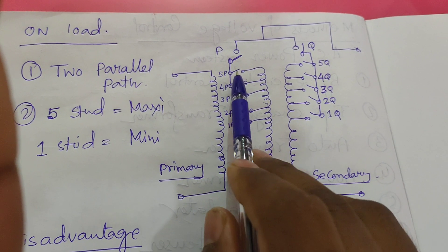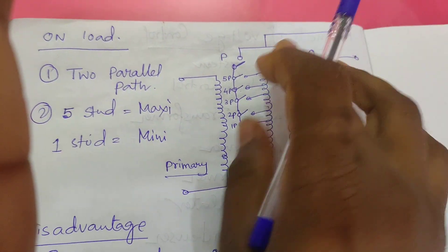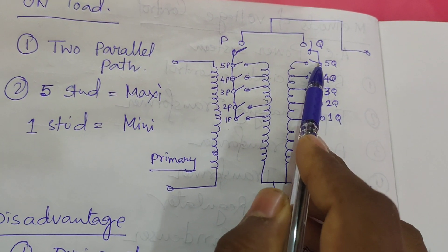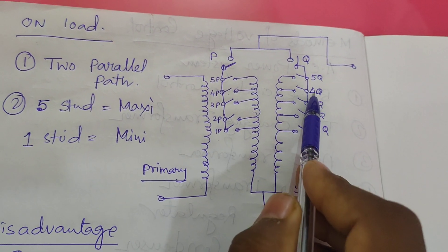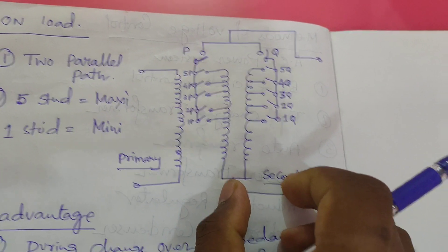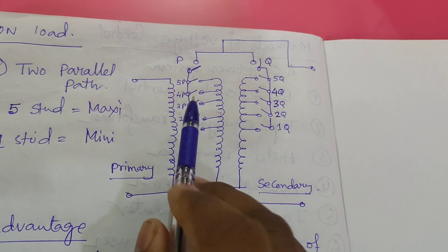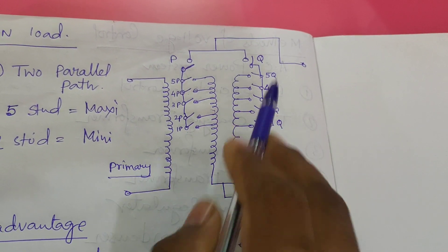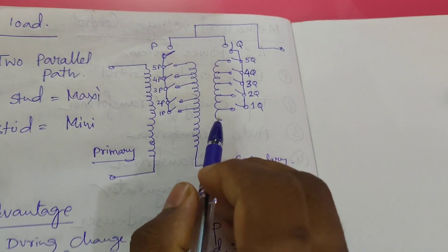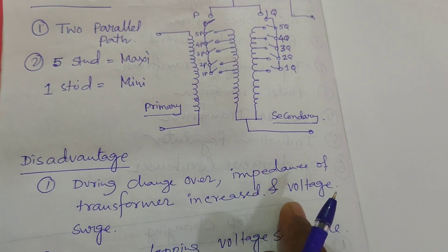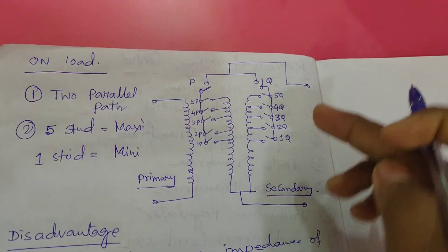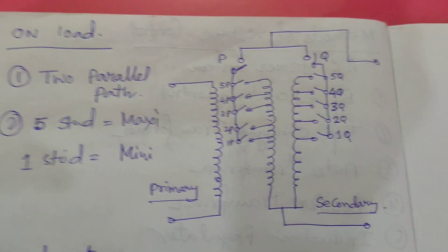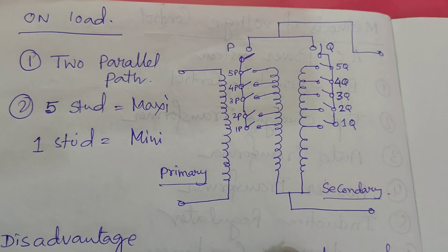After changing 5P to 4P, we reconnect P so both parallel paths are active again. Then we open Q and change the Q arm from 5Q to 4Q in the same manner. During this changeover procedure, the impedance of the transformer increases because the movable arm has resistance, which is factored in during current loading. As a result, a voltage surge or voltage dip occurs during the tap changing, which can trip sensitive relays installed in the system.